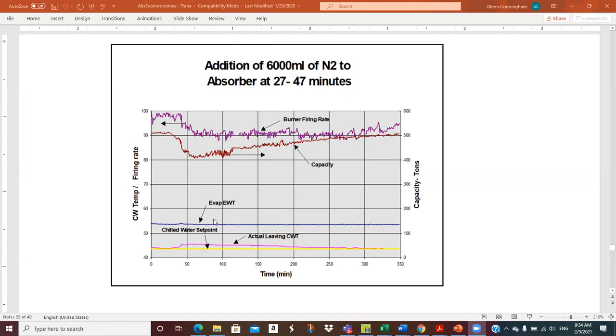And it took a while to get it back under control. But the point they make in the discussion is that when the capacity went down, the old controls would have slammed the heat added in the generator up, which would have led to crystallization. But now the controls are smart enough to realize there's been an air leak in the machine.